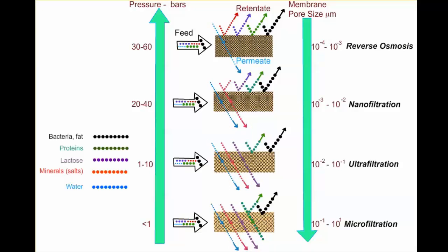The pressure used in these systems also varies. Microfiltration uses fairly low pressures around 1 bar. Ultrafiltration requires 1 to 10 bars, nanofiltration 20 to 40 bars, and reverse osmosis requires very high pressures around 30 to 60 bars.